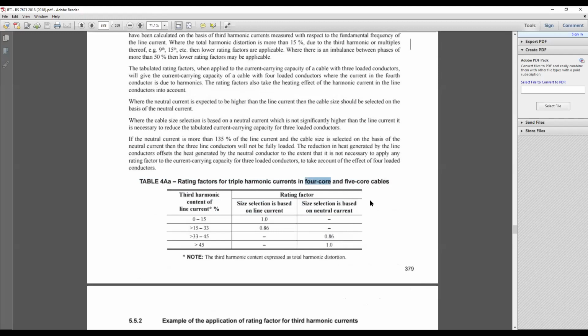cables with many cores. If you are selecting single core cables for all the cores, you do not have to worry about this. You can just calculate the neutral current and select a different cable for the neutral. But when you have a design like this, that means the multi-core cable design, you have to add another rating factor.